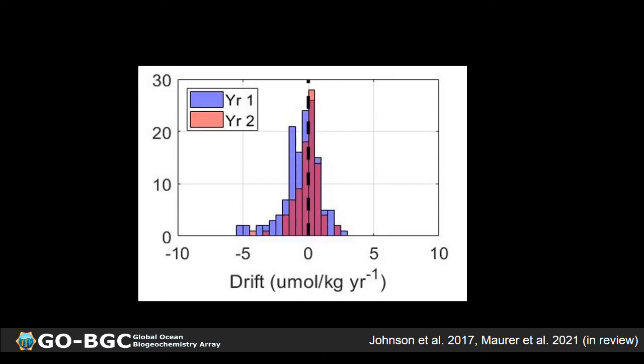So in the first year, the nitrate sensor tends to drift low by up to 5 micromole per kilogram per year. But then in year 2, the drift is now pretty much centered around 0, and the magnitude of the drift is much smaller in year 2. So it seems like these nitrate sensors tend to drift more in the first year, but then it kind of stabilizes over time, which is great.